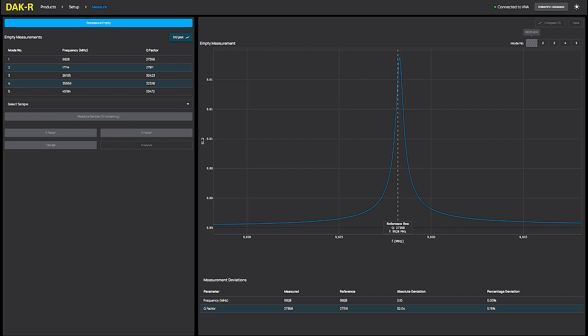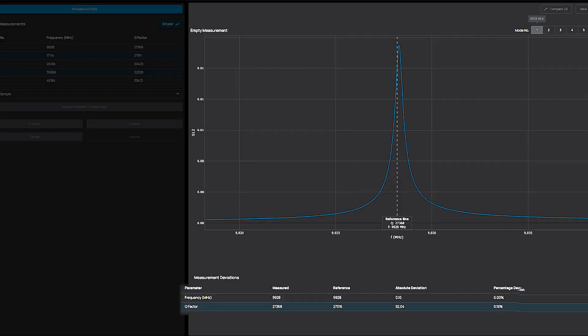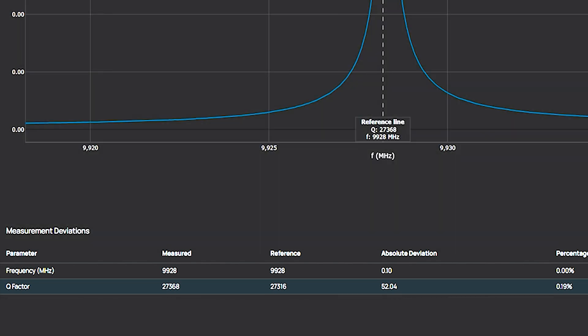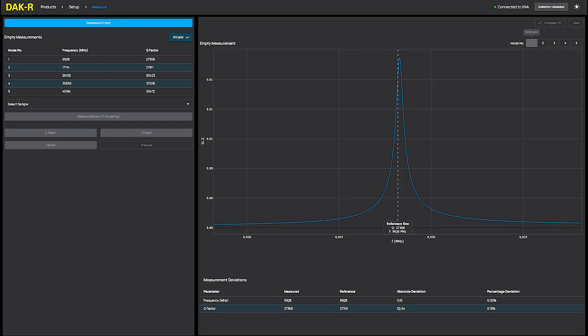I can also view the S21 plots for each mode on the right side of the software interface and can verify that the cavity shows the same performance as during calibration by SPEAG. So, I'm all set and ready to go.